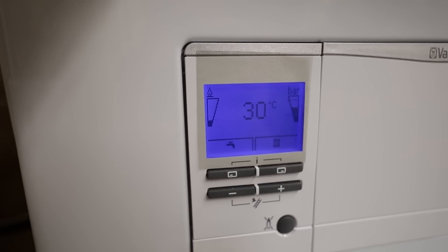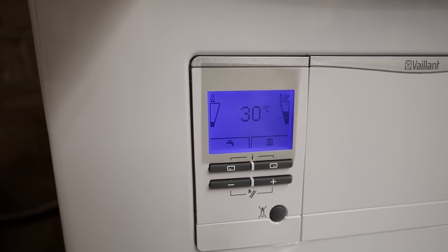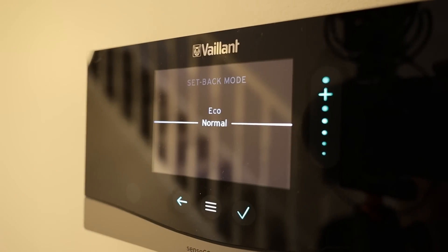Now we can see the boiler running fully weather compensated — 16°C outside, the heat curve is set to 0.9, which gives us about 50°C flow when it's minus 2°C. This little controller is what made me install these boilers again. Those controls give you so many options and the weather compensation is really nice on them.